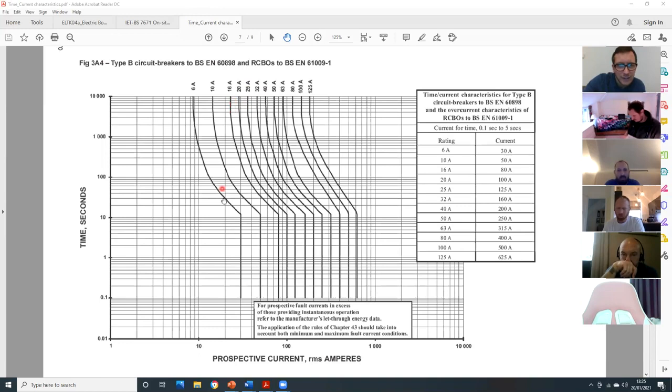If we come down here, it's about a third of the way along the scale between 10 and 100. 1, 2, 3. Yeah, it's closer to 3. So 23 amps. Now, if you divide 23 by its rating, 16 amps, you're getting pretty much the same again, 1.437. So what you can see from these two types of devices is that they've got a very similar fusing factor.